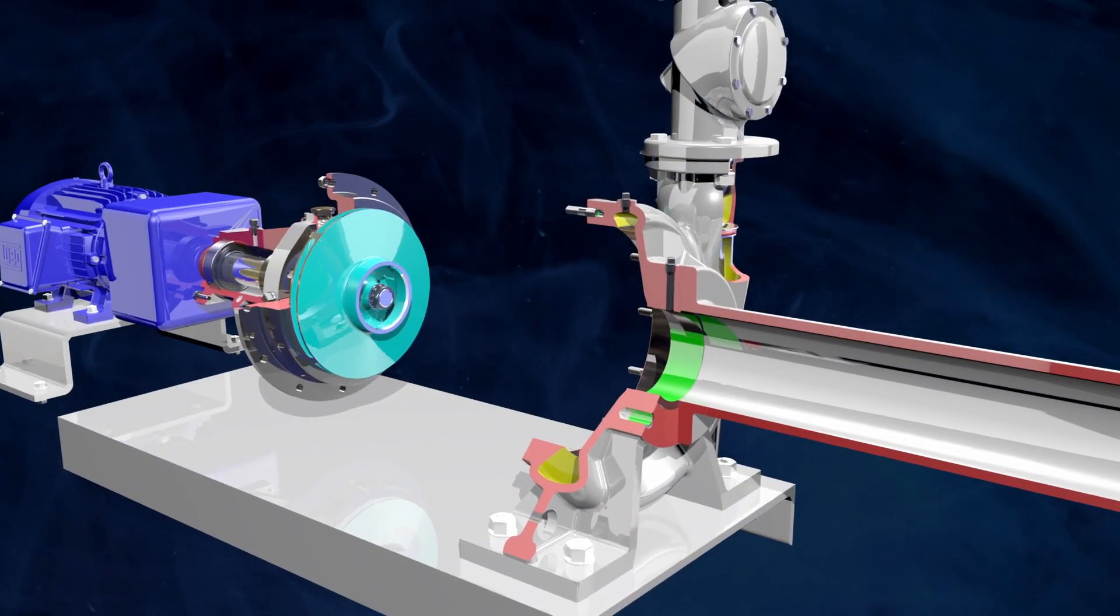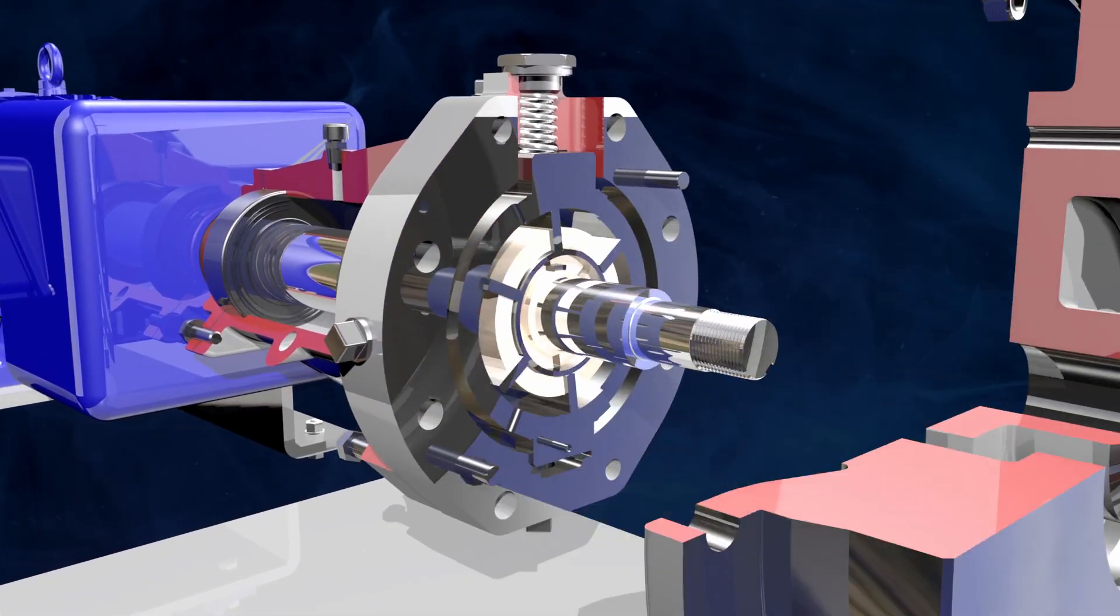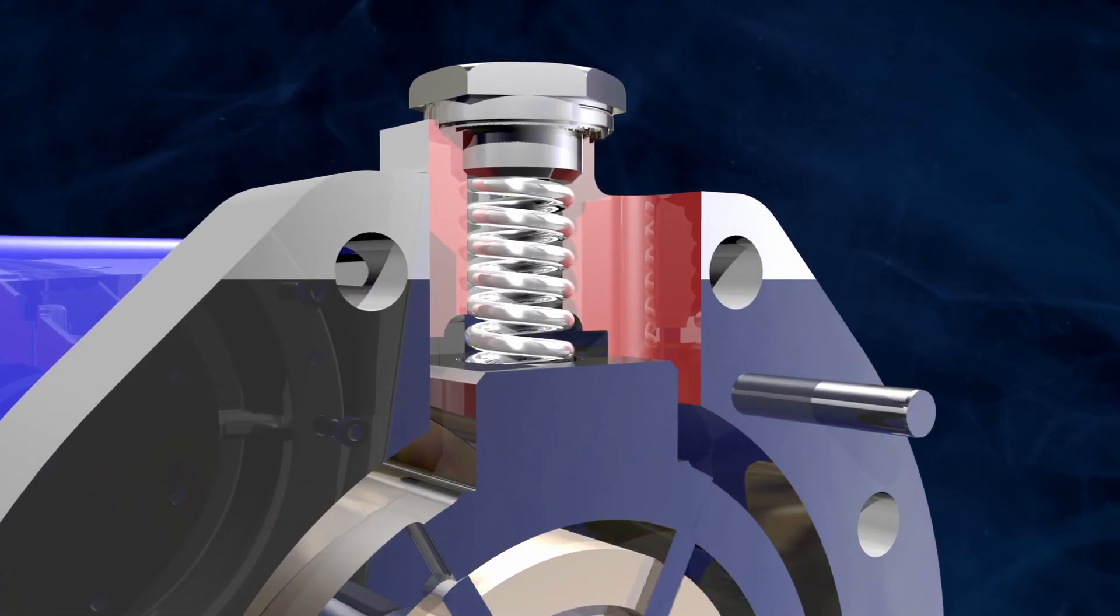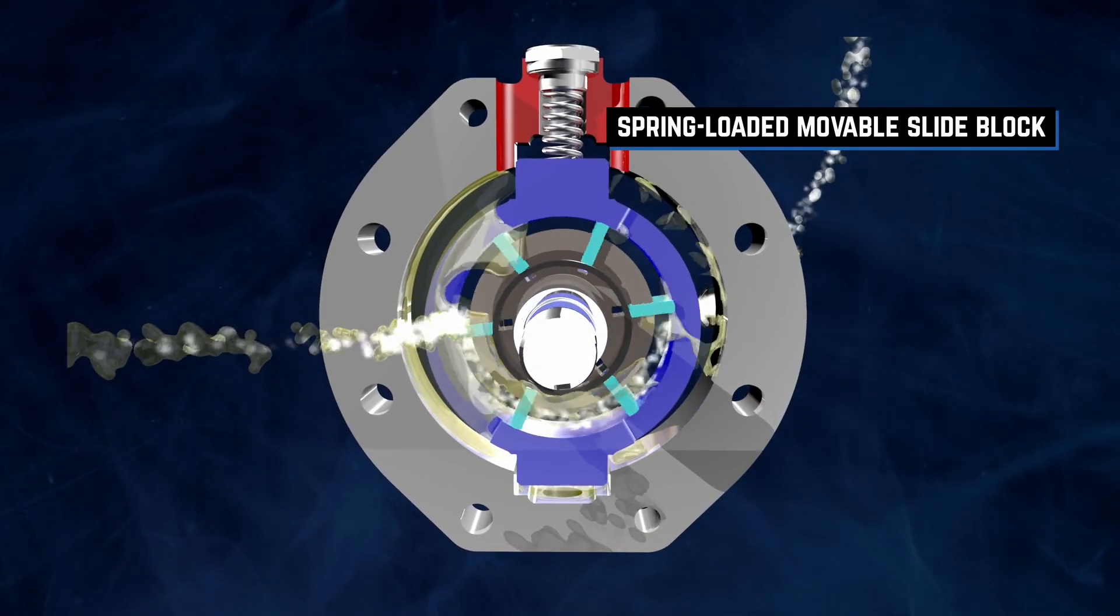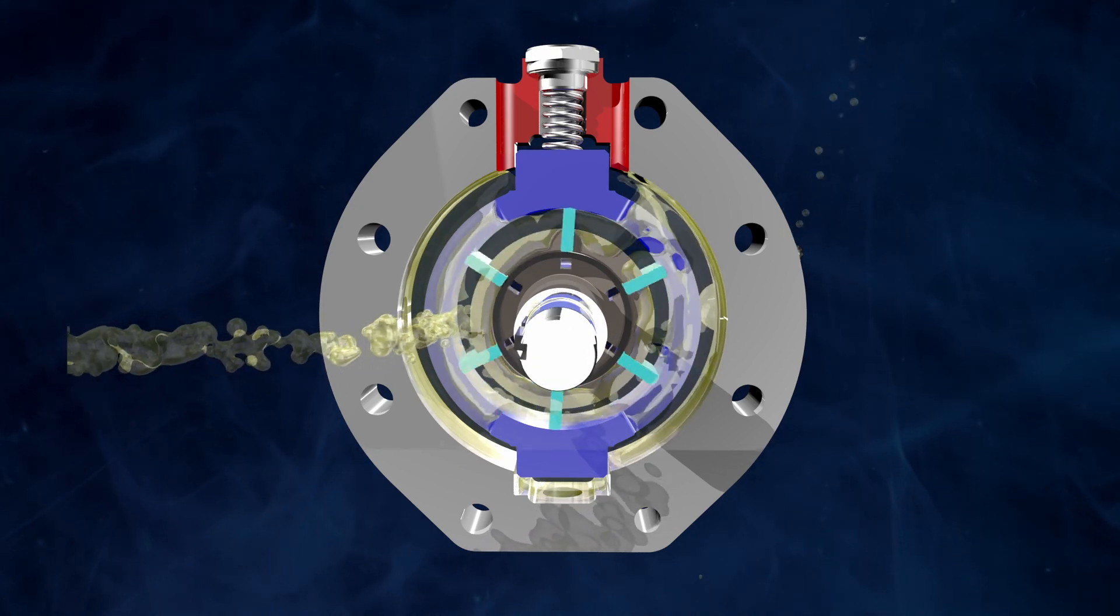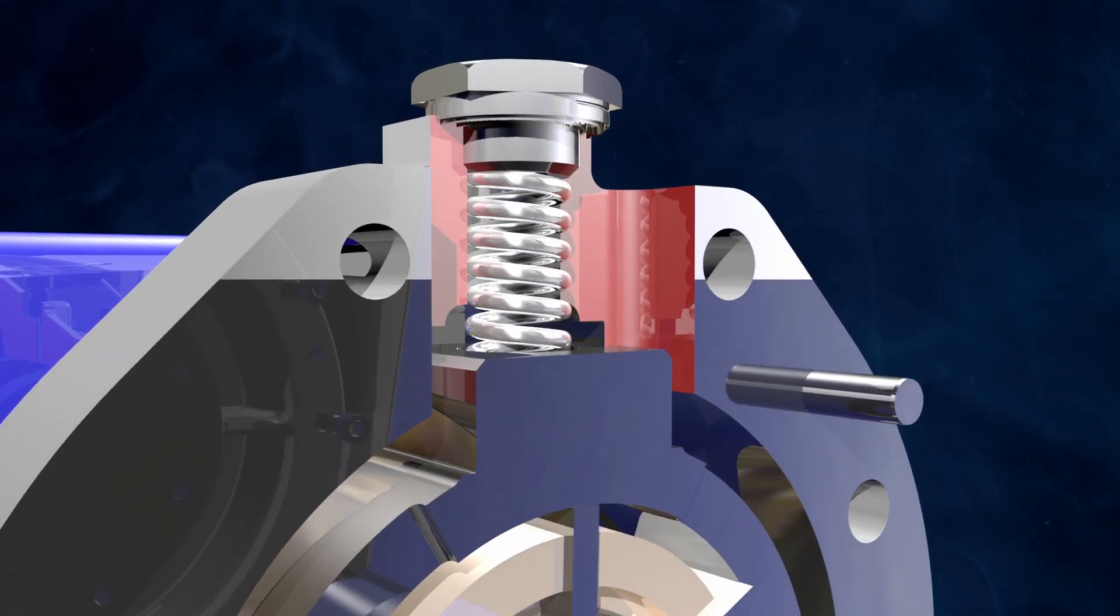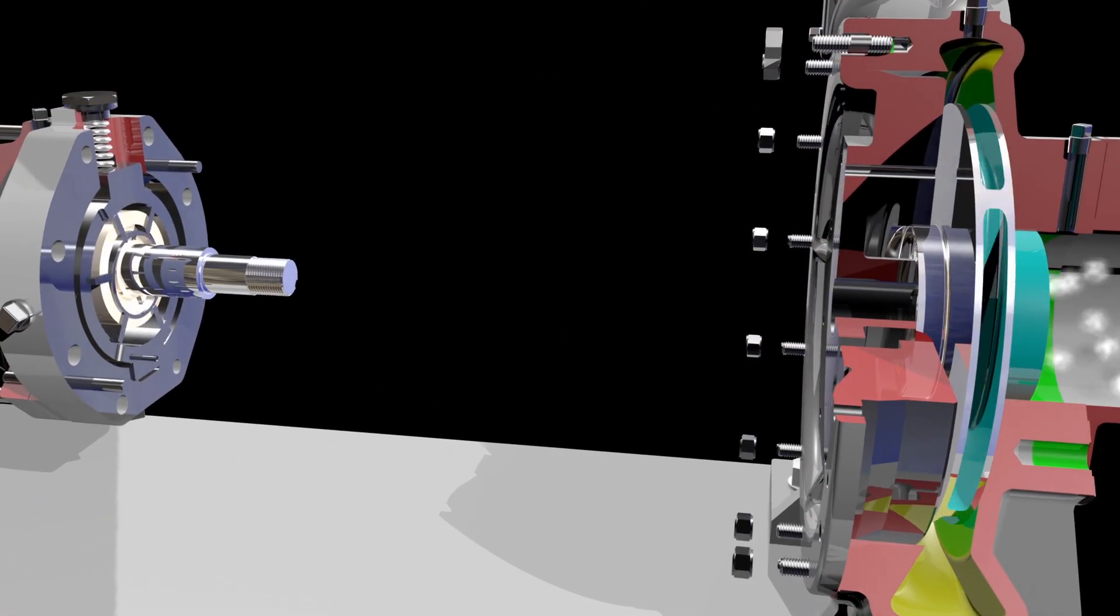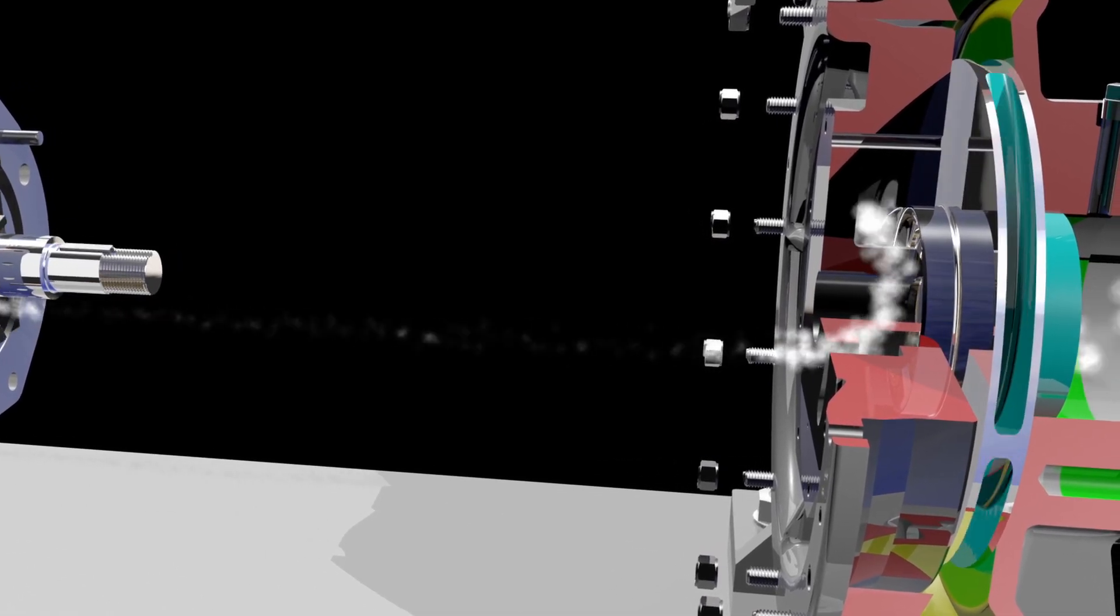At the heart of Rotoprime's integral pumping system is the variable capacity priming pump. Powered by a spring-loaded, movable slide block, it draws air and vapors through the volute suction, compresses them, and exhausts them downstream via external bypass tubing. With the slide block set to maximum eccentricity, the priming pump can handle up to 18 gallons or 68 liters of air per minute, running at 1,750 RPM.